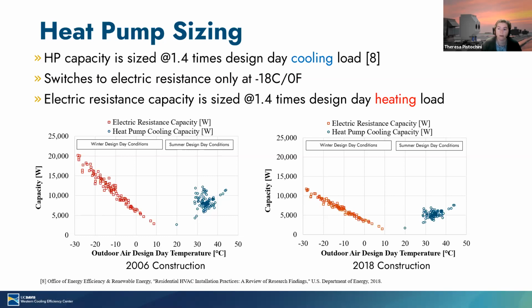You can see how the heat pump cooling capacity and electric resistance capacity were sized in all of the cities simulated. As the outdoor design day temperature decreases, the electric resistance capacity is larger, and as the outdoor air temperature increases for the cooling design day, the heat pump size increases. What's significant here is that you can see that the heat pump was smaller in the 2018 construction year because the building loads are lower.